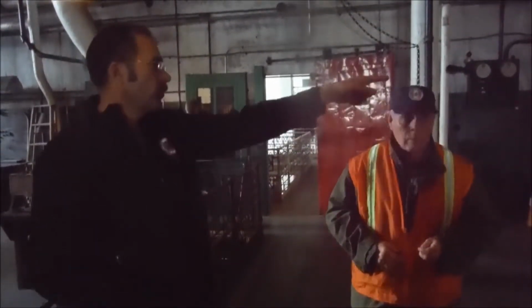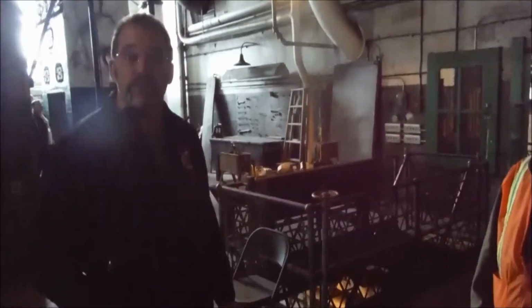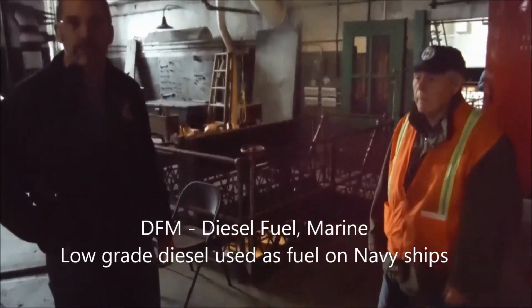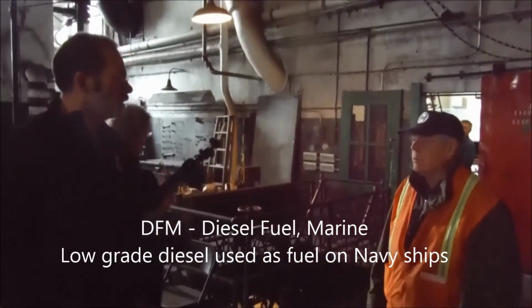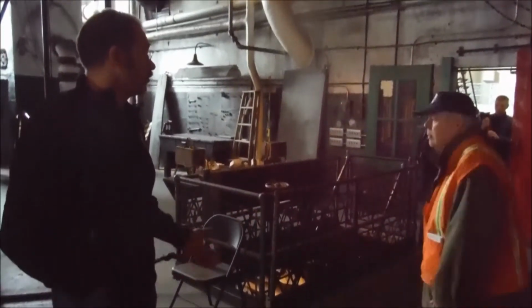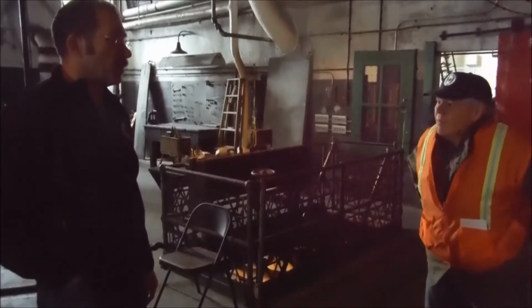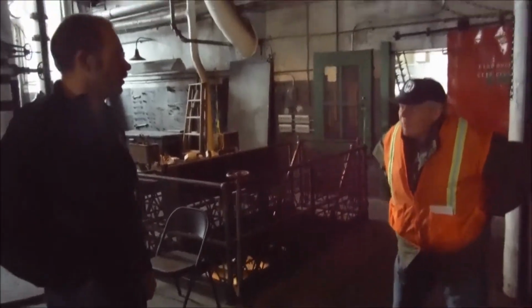And what's this over here that was behind us? That and that are fuel oil heaters. The oil is just enough to flow. Fuel oil heaters? Because the fuel oil back then was so thick and gooey that if you didn't heat it up, it wouldn't flow and it wouldn't atomize. We preheated the fuel oil even on the Flint, even though it was DFM, because if it was warmer, it atomized better and burned more efficiently. The BTs did it all. Well, on the destroyer your dad would have been on, that would have been a real old black oil destroyer, practically burning tar. Exactly.